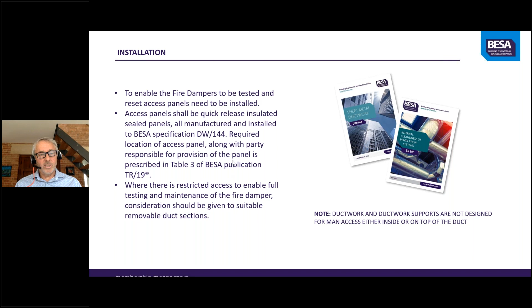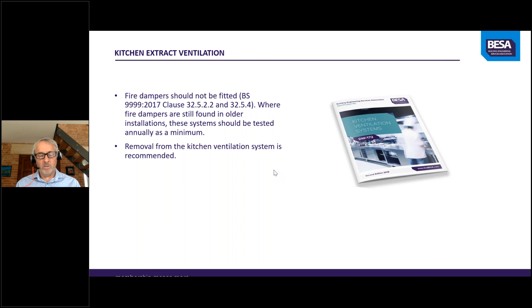Kitchen extract ventilation. Well, BS 9999 again will tell you that you shouldn't have fire dampers in kitchen extract ventilation systems. You may still find some dampers in old systems, and if this is the case, then they should be tested annually as a minimum. But ideally, really, you should plan to have the fire dampers removed from the kitchen ventilation system. We would strongly recommend that. And again, the BESA standard specification for kitchen ventilation DW172 will actually also tell you this, as well as with many other items. Next slide, please.